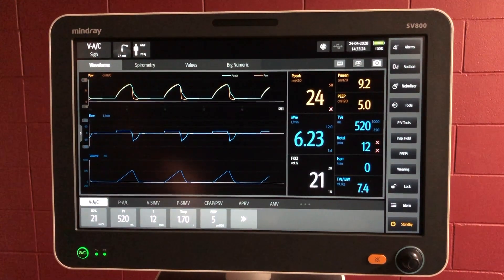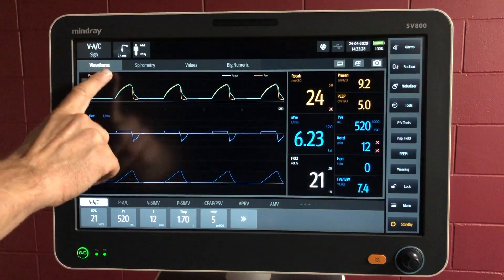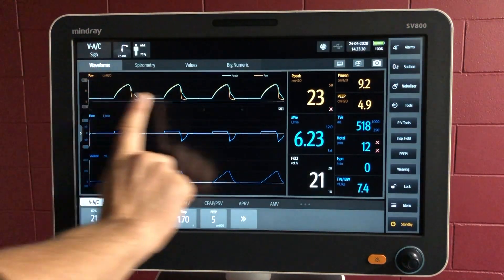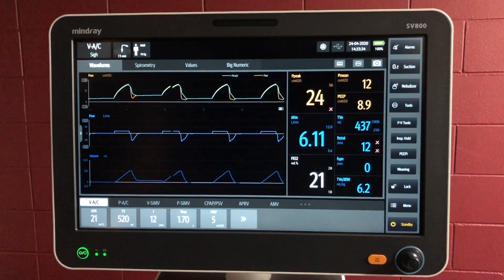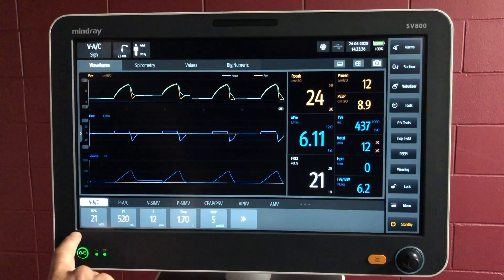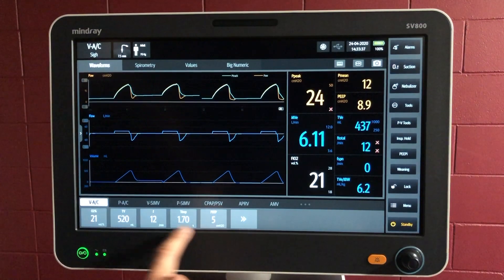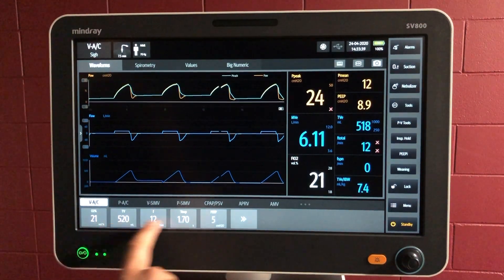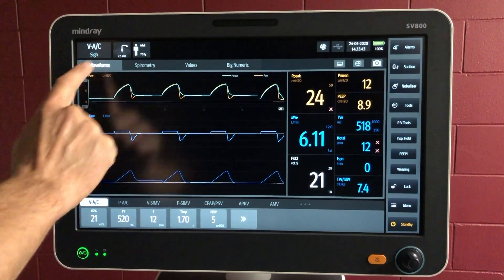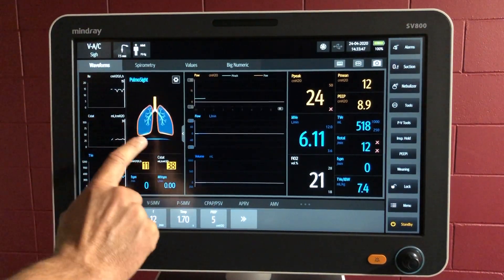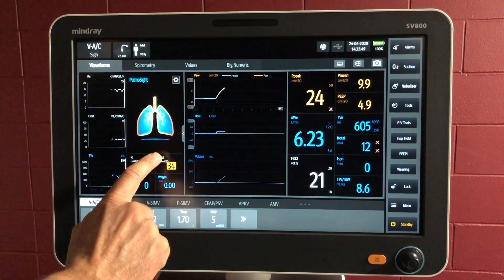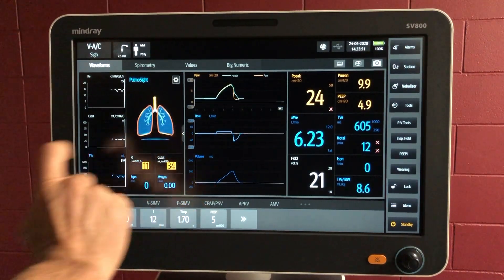Let's have a look at some viewing options of the main screen. As a default we've got the waveforms tab open, which gives you a large amount of surface area to view the waveforms, with the readings over here and the settings underneath. The settings will always stay there. From within the waveforms page we can pull out this PulmoSight window for lung compliance, and we can tuck it back in as well.